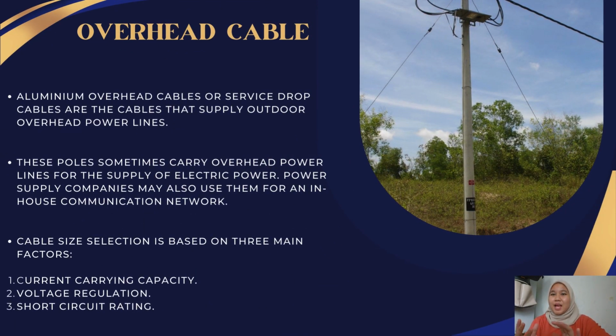Overhead cable. Aluminium overhead cables, also known as service drop cables, are the cables that supply outdoor overhead power lines. These poles sometimes carry overhead power lines for the supply of electric power. Power supply companies may also use them for an in-house communication network. Other than that, cable size selection for overhead cable is based on three main factors, which are current carrying capacity, short circuit rating, and voltage regulation.